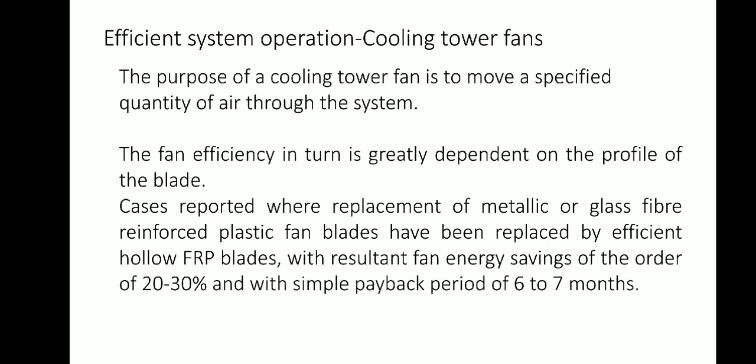Cases are reported where metallic or glass fiber reinforced plastic fans have been replaced by efficient hollow FRP blades, with resultant fan energy savings of the order of 20 to 30% and with a simple payback period of 6 to 7 months. Also, due to lightweight, FRP fans need low starting torque, resulting in use of lower HP motors. The lightweight of the fans also increases the life of the gearbox, motor and bearing, and allows for easy handling and maintenance.